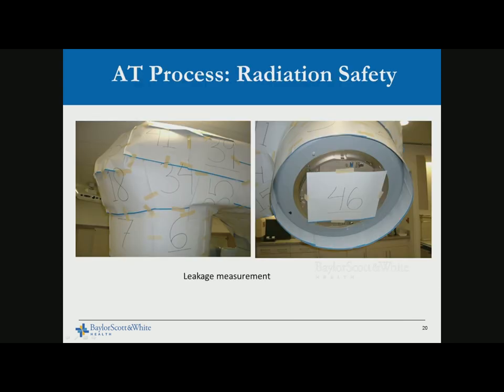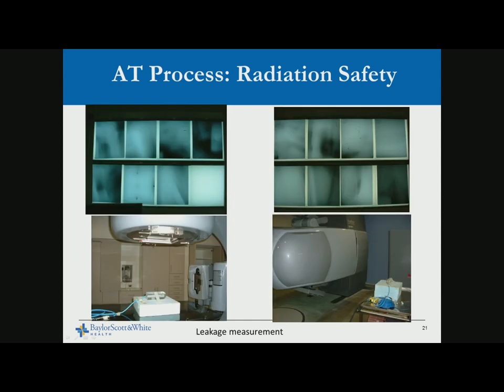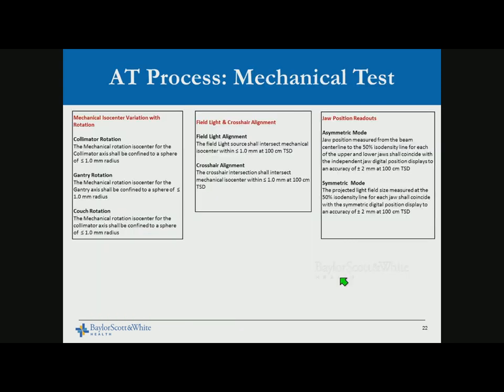For the leakage measurement process, first identify the highest spot of leakage by wrapping things around the LINAC, closing the jaws, and delivering high monitor units. Once you identify the highest leakage spot, make a measurement at isocenter and at one meter from the source to determine whether it is 0.1% of the isocenter dose. These tests need to happen sequentially: general safety, then radiation safety, then mechanical tests.